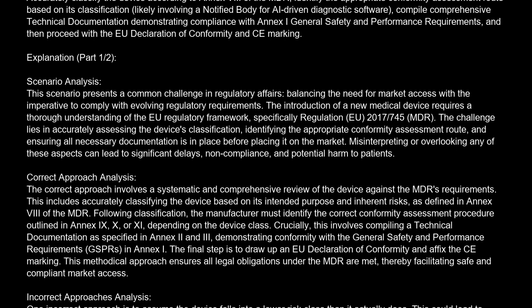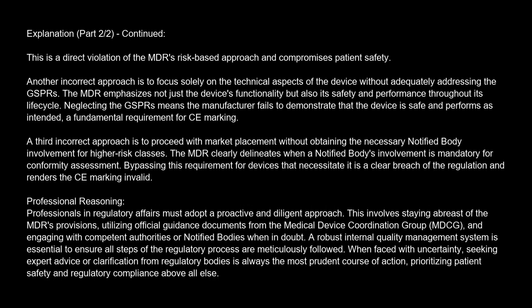One incorrect approach is to assume the device falls into a lower risk class than it actually does. This could lead to selecting an inappropriate and less stringent conformity assessment procedure, bypassing essential safety checks, and potentially placing a higher risk device on the market without adequate scrutiny. This is a direct violation of the MDR's risk-based approach and compromises patient safety.